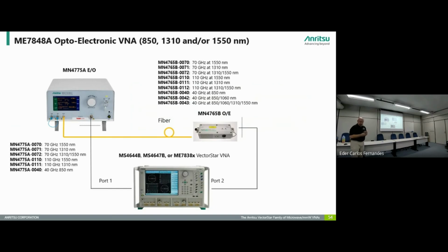And in the application, we put the two together, and now we have an E to O and an O to E. And depending on what we measure, we substitute one for the other. So if we're measuring an E to O device, obviously this wouldn't be here. We use the O to E module, measure whatever is here, de-embed this, and we have a measurement of the modulator. If, however, we want to measure an O to E device, then we need the characterized E to O converter. And we get that characterization by using the OE module to characterize, and then we can de-embed the O to E or the E to O when we're measuring a photodiode. So either way, we're just doing a simple de-embedding. But again, we need to know what the file is. So we need that characterization. And it has to be derived from national standards to be of any use.